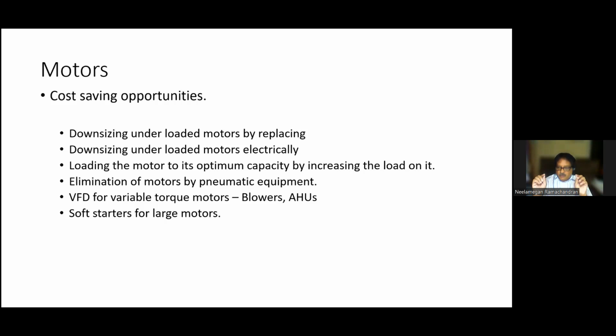where you need only two speeds, or only a reduction of speed once in the lifetime of the motor, it is a waste using a VFD drive. We have so many other methods where we can reduce the speed of the motor and forget about it. It can run at that speed. Where we require frequent speed variation, there we can put the VFD. I am insisting on this because I know maintenance engineers who lost their credibility by simply fitting a VFD and not getting the desired result. It was because it was a constant torque application. They just fitted the VFD saying there would be that much saving, but the expected saving was not there.